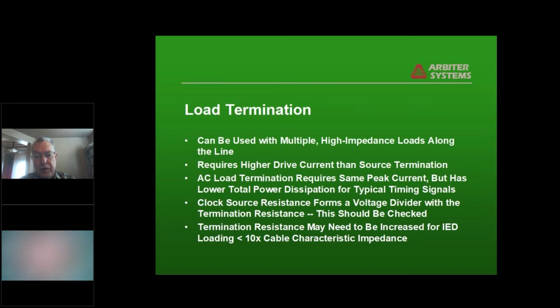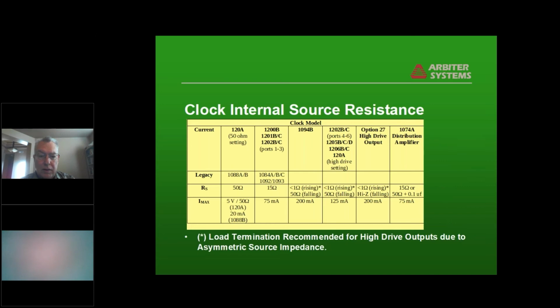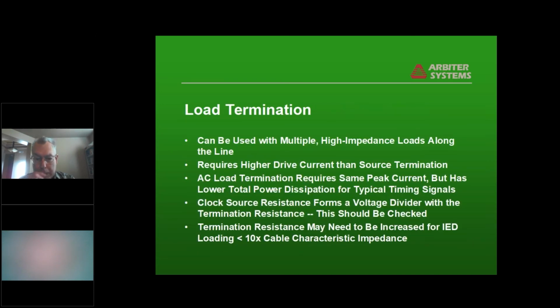So those clocks at a 15 ohm source impedance in the chart there, the 1200, 1201, 1202. If you use a load termination, it's going to cause that voltage to drop to around 4 volts, which is usually okay, but you have to check and make sure it works. And the termination may need to be increased a little bit if you have a lot of IEDs, and the IEDs load the signal. They basically act as a load in parallel with the termination resistance, so you might need a 60 ohm load instead of a 50 ohm load.